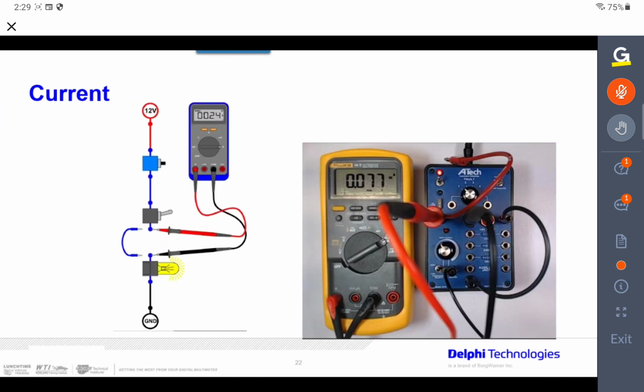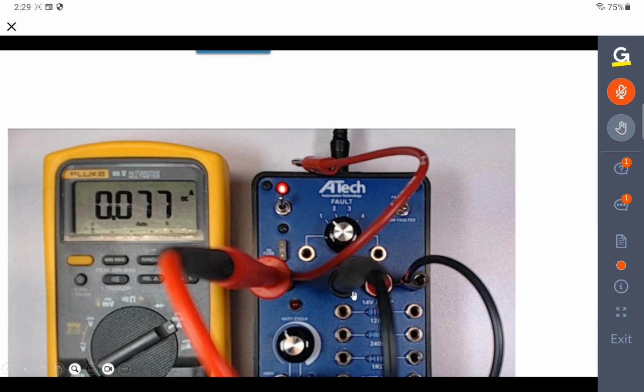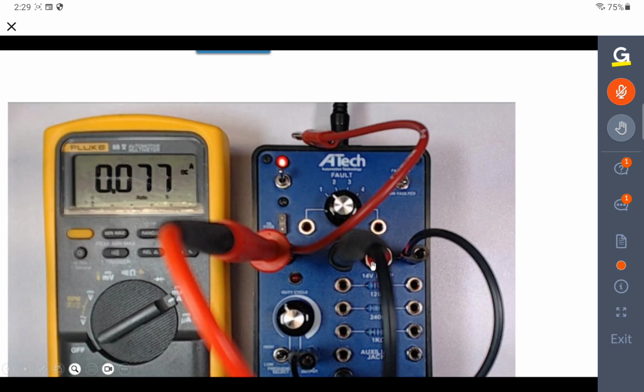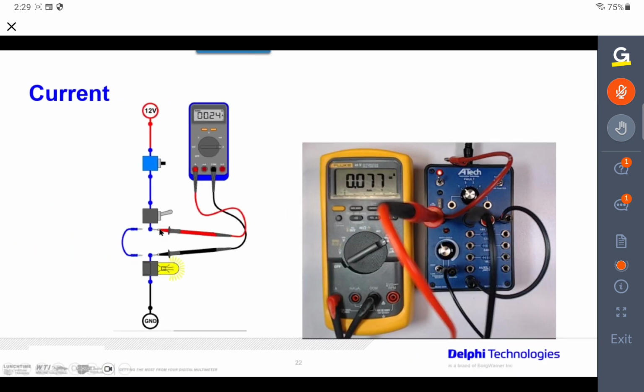Current - notice I have to take the leads out and put my leads in place. So if you look carefully at what I've done on this particular one, I took my red lead out, I took my black lead and back probed at this point. So I am checking the current going across this circuit as it's feeding over to my light bulb. You can't see it's there, but it's there. And I'm at 0.077 DC amperage, so I'm looking at it. Again, I have to break into the circuit with a current probe, and you want to do it after the switch.